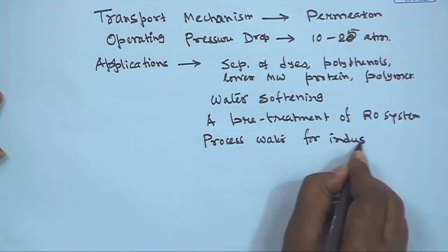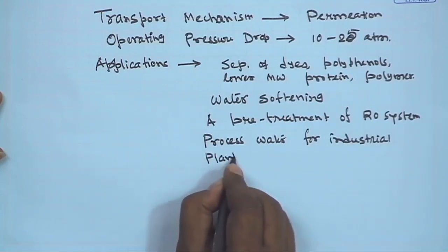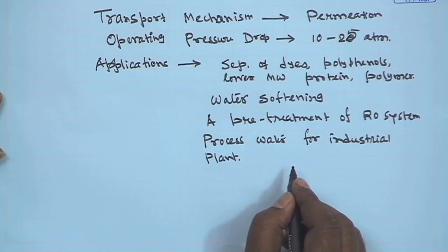Nanofiltration is also used to produce process water for industrial plants. If saline water is used as a utility stream in a plant, it causes corrosion of pipelines. Nanofiltration can be used for softening to remove salts, calcium, and magnesium, so that deposition and scaling of pipelines is reduced. So nanofiltration has quite different and varied applications.